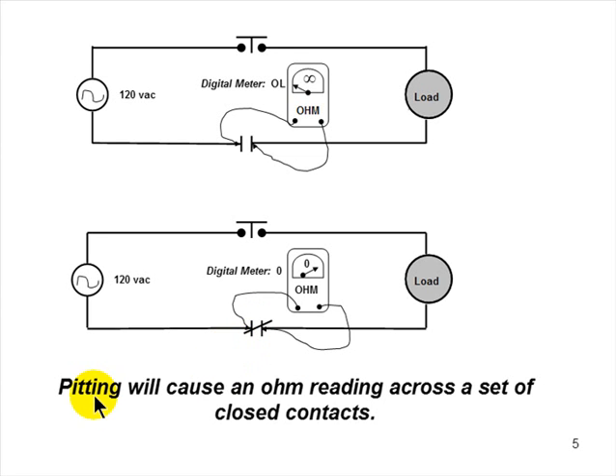And pitting tends to become, corrosion tends to become exponential. You might have a 1 volt drop today, tomorrow it's going to be 2, a week from now it's going to be 4, then 8, then 16, and when you get up to around 12 volts, 10 volt drop across a contactor, you smoke the load it's attached to. The motor, the compressor, whatever else.